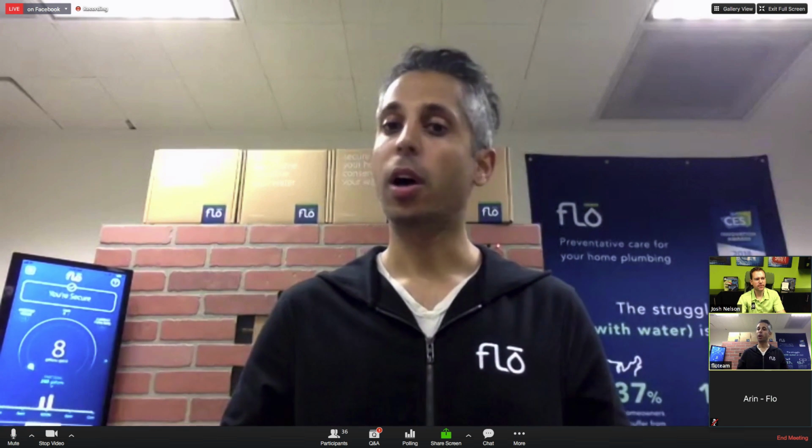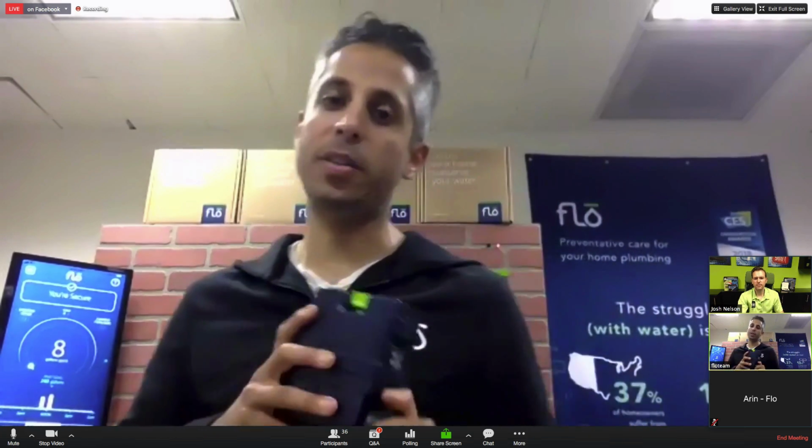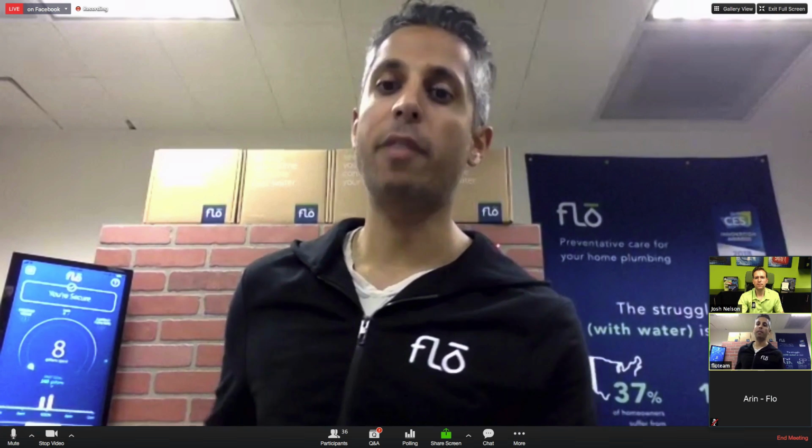Yeah, good question. Hard water doesn't affect the unit. There is a turbine, that's the kind of flow sensor we use, but hard water just kind of comes right off of it. So we haven't experienced any issues with hard water. What we have experienced issues with is certain well systems where the water is not being treated well before it goes through the flow device, and there are certain magnetic sediments in the water, which can have a tendency to mess a little bit with our flow sensor. So if there are conditions where there are a lot of magnetic sediments in the water, we would recommend installing the flow device after the water treatment system. That's the one place where the quality of the water could have an effect on the system.